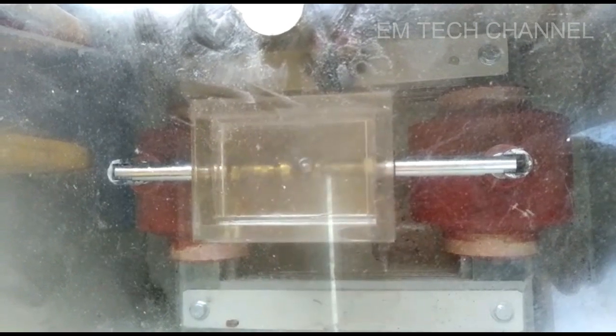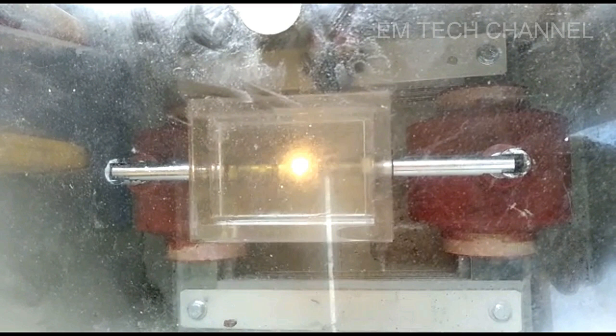As the oil between the conductors lost its insulating property, it became a conductor, and as it became a conductor, the two electrodes will become a short circuit and it trips the kit. The voltage at which this oil loses its insulation property is called breakdown voltage.